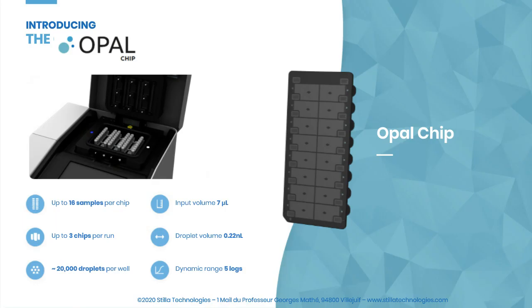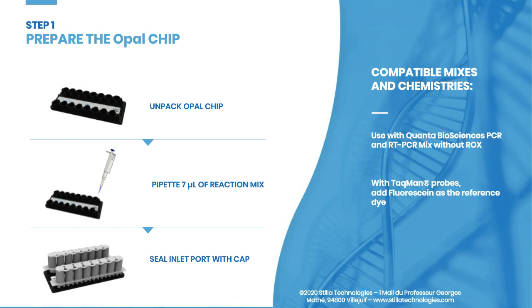The new consumable which Elise and her team used to set up the validation of Crystal Digital PCR for chimerism monitoring is called the Opal chip. A single chip can accommodate up to 16 tests at a reaction volume of seven microlitres each. The Naica system can handle up to three chips simultaneously, giving the flexibility to handle up to 48 tests in a single run. Each reaction is split into approximately 20,000 droplets, enabling a theoretical dynamic range of five logs. Handling the chip is a simple process — it contains only a single pipetting step after removing the seal. The layout allows use of standard single or multi-channel pipettes already available in each lab. Afterwards, the chip is sealed with a PCR cap and ready to be processed in the NICA system.